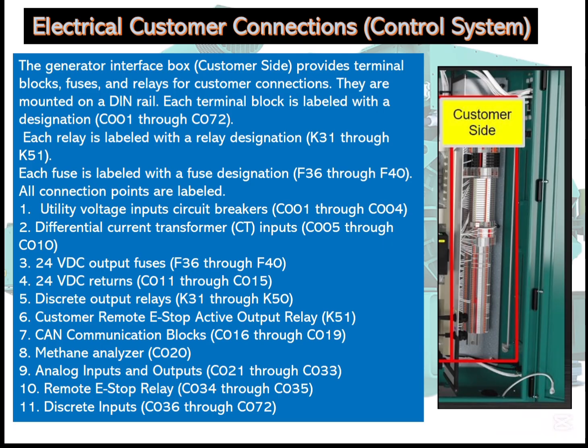We can choose what we require according to our systems. All the outputs must be chosen for our site. Different sites have different requirements. Different plants have different requirements. So we need to look at what our own requirement is, and we will select those connections and the inputs we want to apply. All those inputs are remote start, load demand stop, U20CB in, U20CB out, GCB in, GCB out, open, close. All of them are available on this customer side.